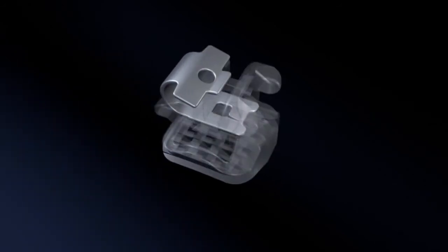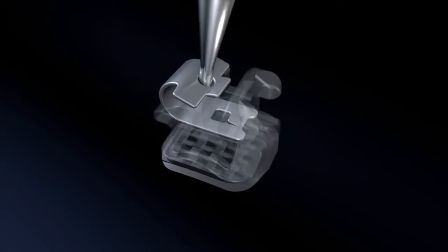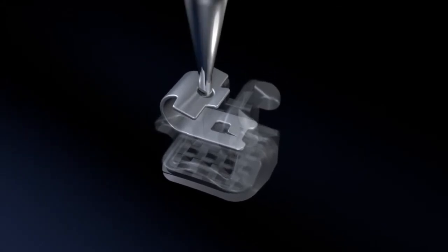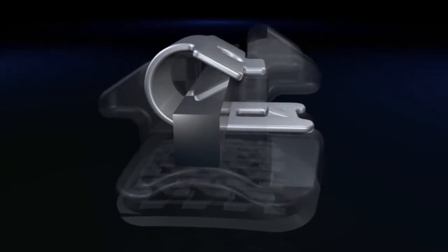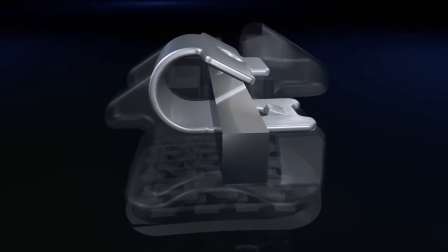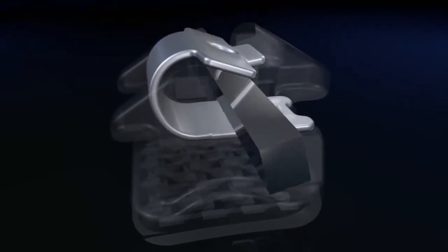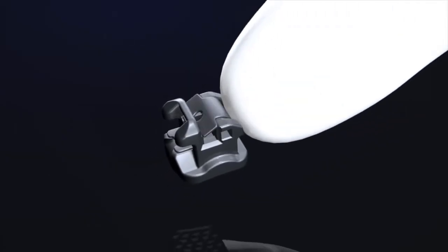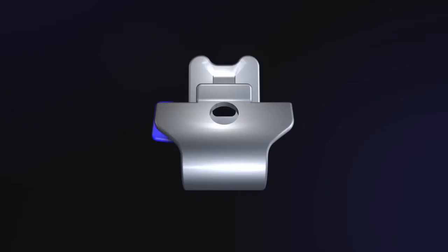The clip itself has been completely redesigned. The material is thicker, making the clip less susceptible to deformation. What's more, the increased thickness of the clip makes it more powerful and makes angulation, rotation, and torque more controllable. The clip now closes with a distinct click.